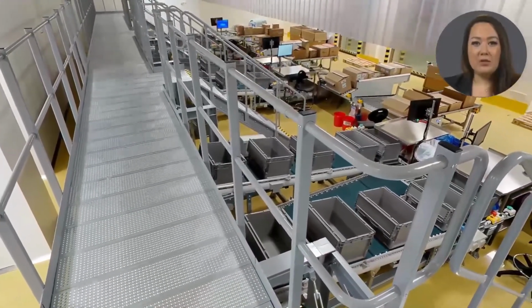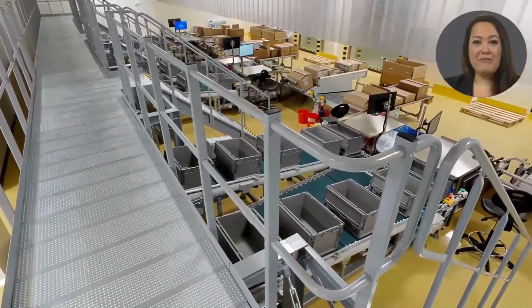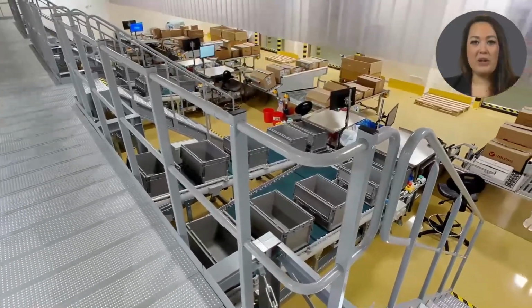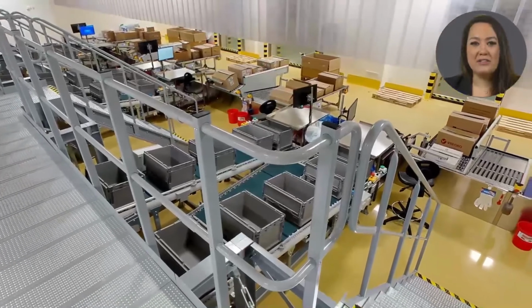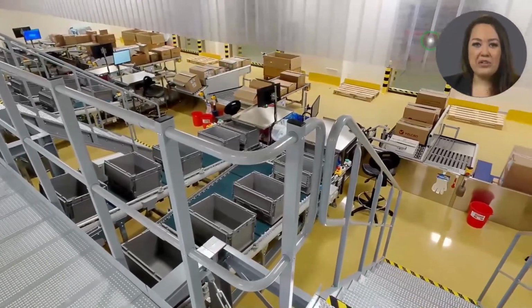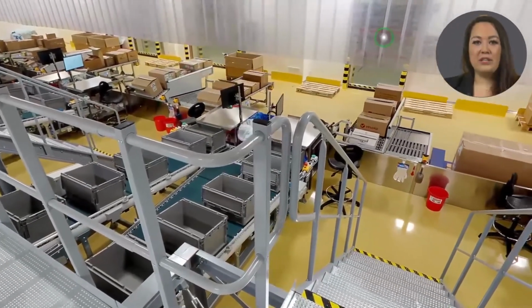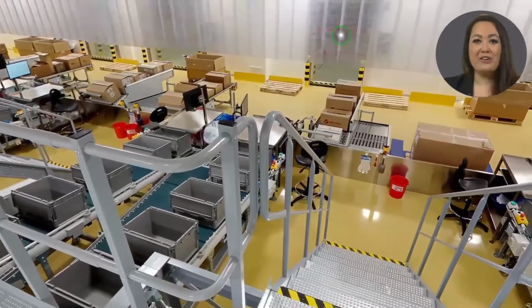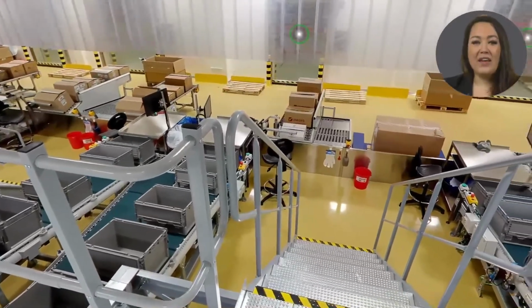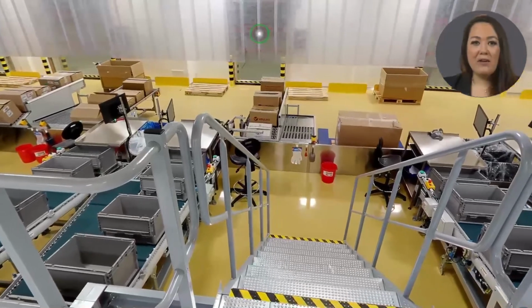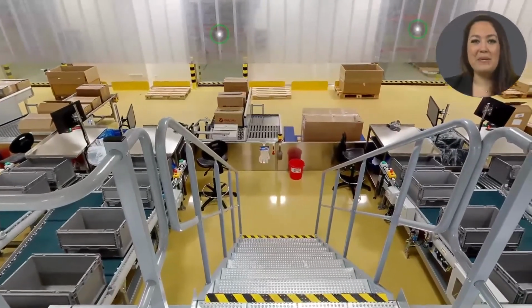Our semi-clean rooms have an overpressure of 5 Pascal to prevent particle migration from the surrounding areas. This overpressure is cascaded through to our clean rooms, which have an overpressure of 10 Pascal. In total, our clean room area is 22,000 square meters.